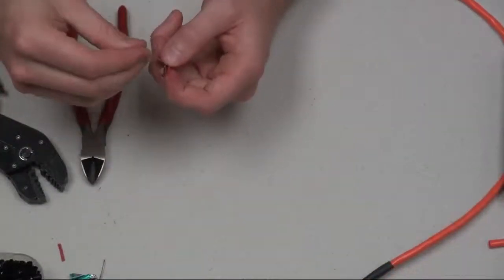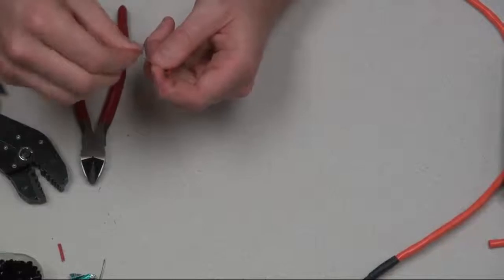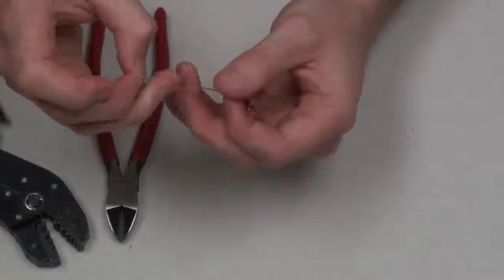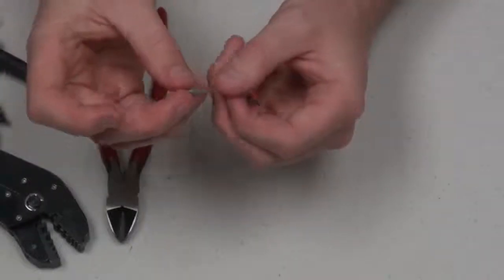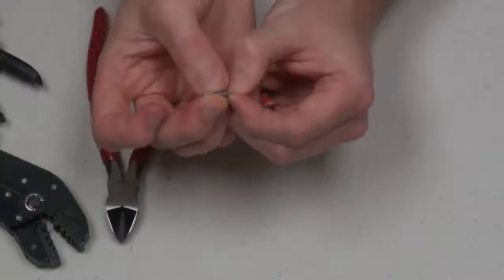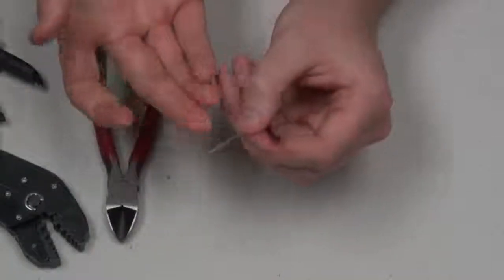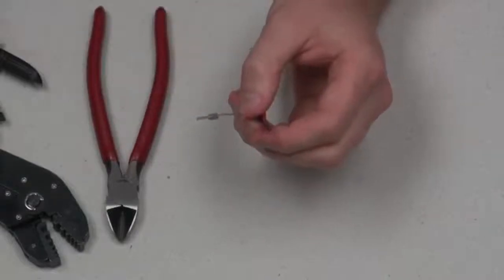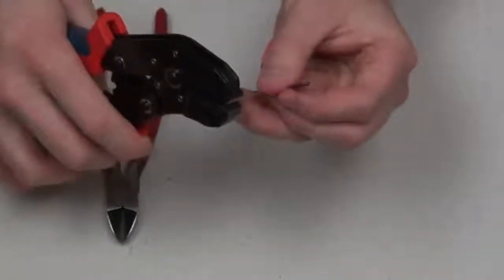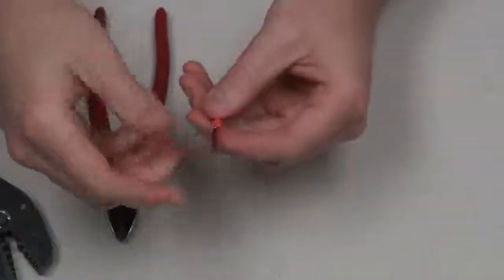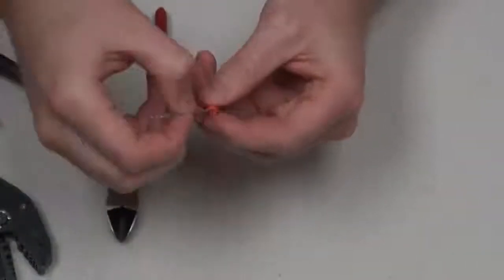Now, of course, two wires here. To go ahead and just be done with the shield wire, at this point, I like to just go ahead and ferrule it. It's a little bit different. You've got to be careful not let this thing slide down the cable too far. But again, if you're using the right size, it should sort of want to hang by itself right on the wire. So we'll go ahead and ferrule and crimp this thing. Crimp it nice and tight. There we go. So that one's all ferruled and out of the way.